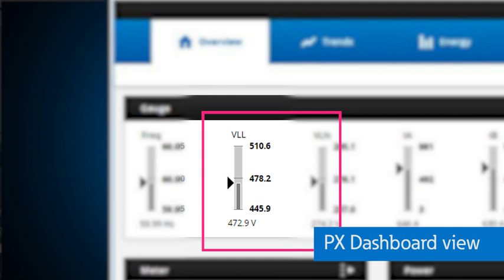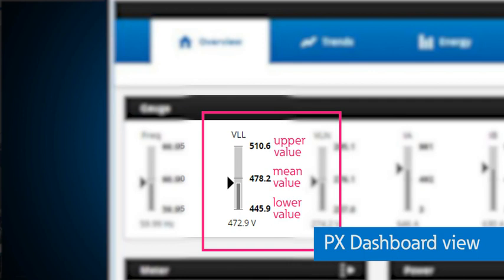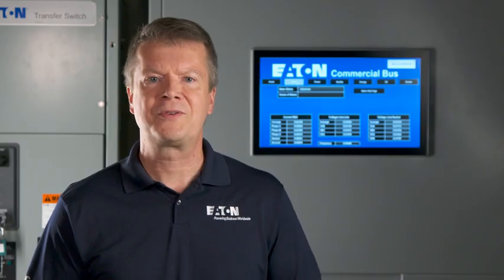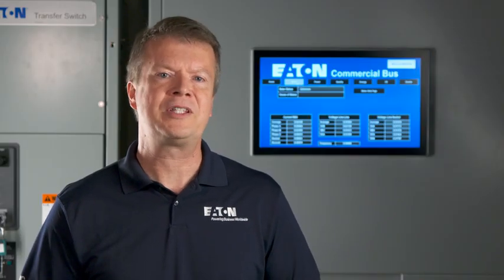This graphic doesn't show you what your 480V system should be, but rather it shows you a statistical view for how your system is doing compared to its historical normal parameters. This view shows the statistical average for each value and indicates an upper and lower statistical range representing plus 1 and minus 1 standard deviation around the mean value — in other words, the signal falls somewhere within this middle range 68% of the time.